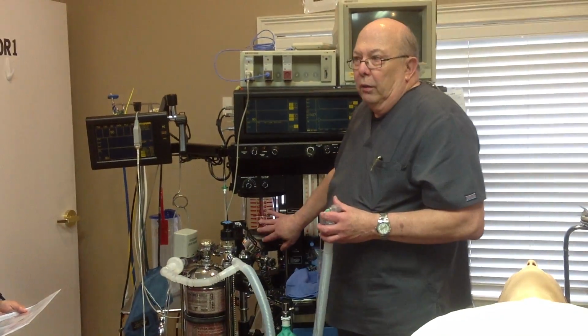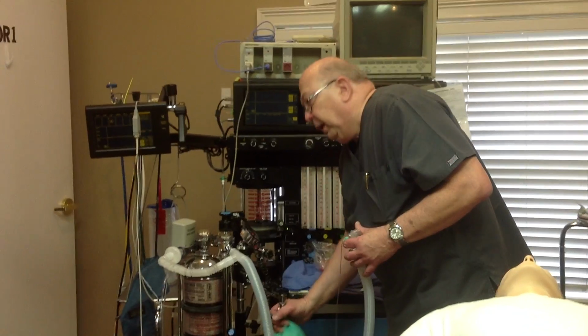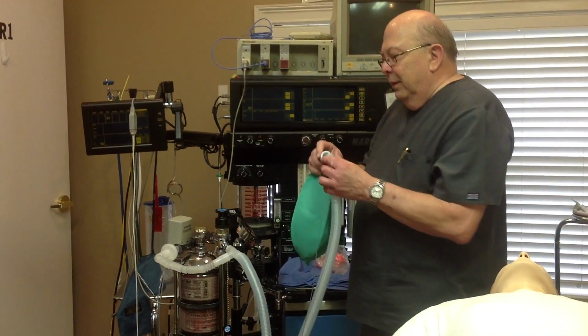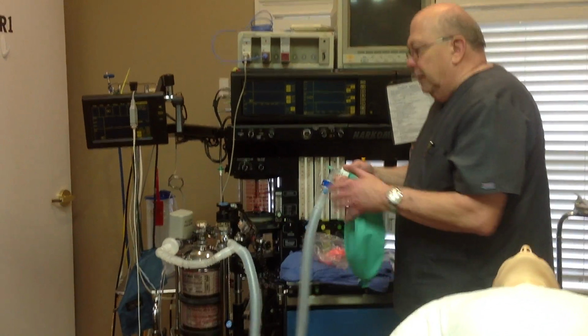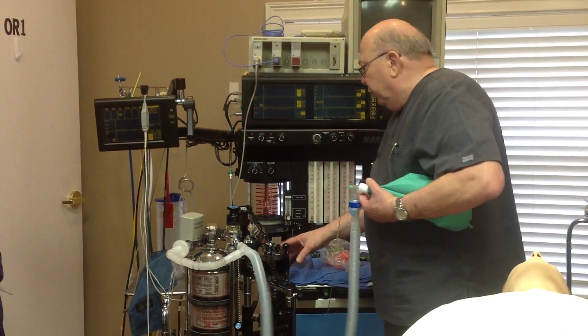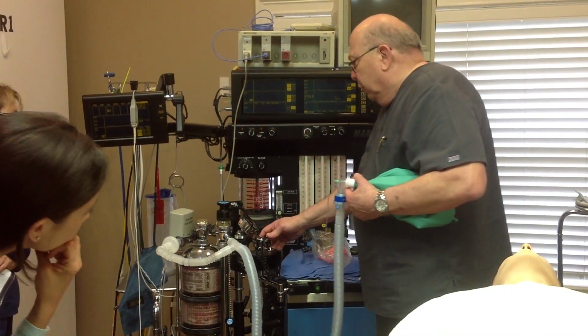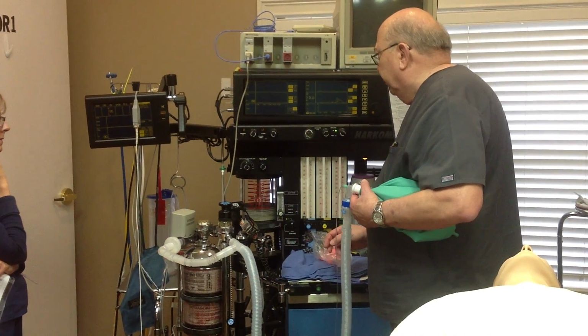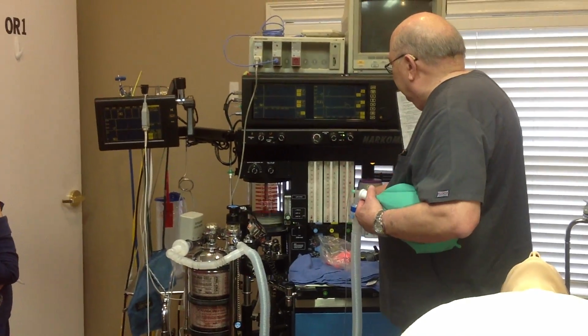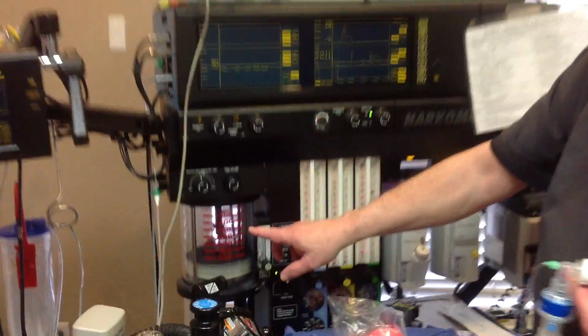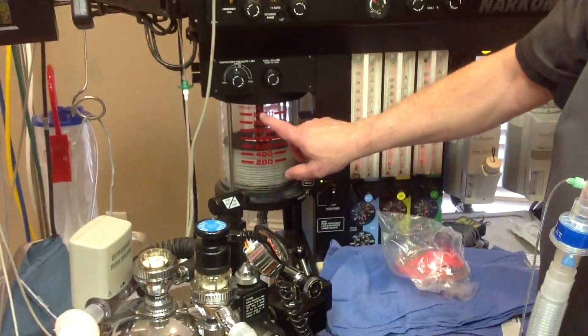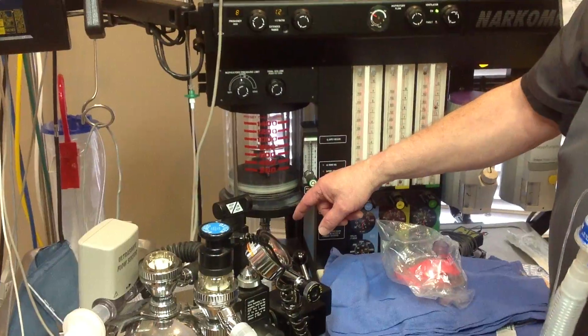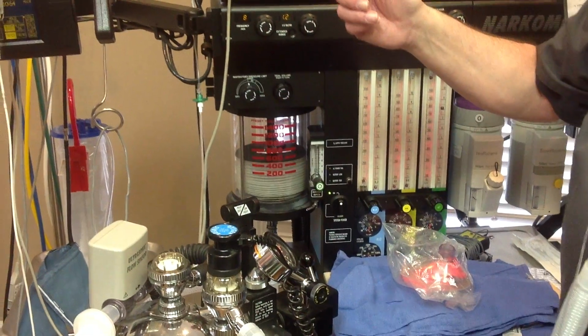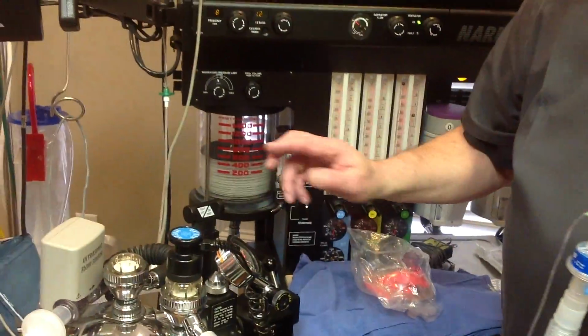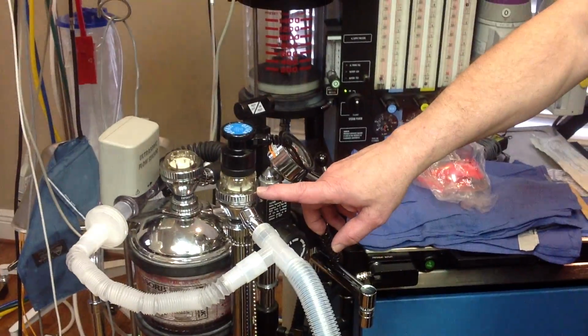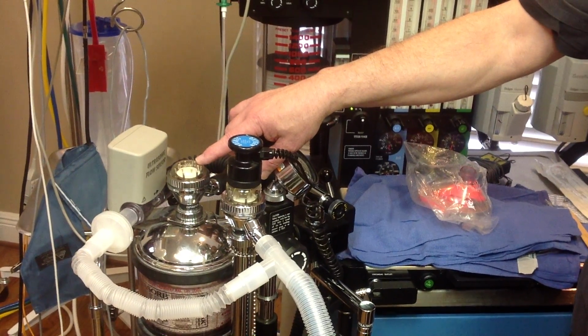I'm going to check my ventilator at this point in time. So I need to have a lung that has compliance to it. Okay? So I take that off, put that on here. So now I'm going to switch from bag mode to auto mode, which is your ventilator. So I make sure that it's turned on. Make sure I have a gas flow. All right. Now, when the ventilator descends, that's inspiratory, comes back up, expiratory. So I know that's working. Now I'm going to look at my valves. Breathe in, it fluttered. Breathe out, it fluttered.